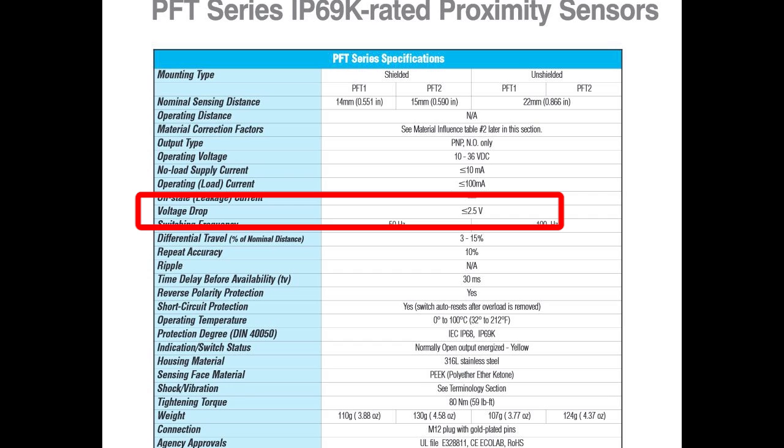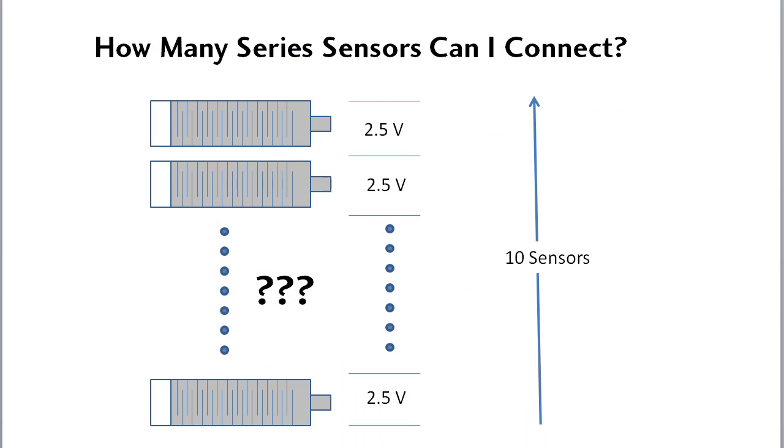Looks like this one is 2.5 volts. So if I have 10 sensors in series, they would need 25 volts, but I only have a 24 volt supply so that isn't going to work. So the maximum number of sensors in series depends on how much voltage you have available to drop across all of the sensors.